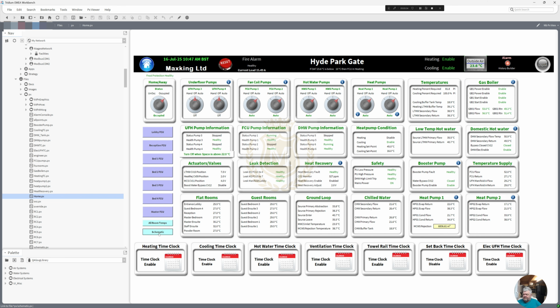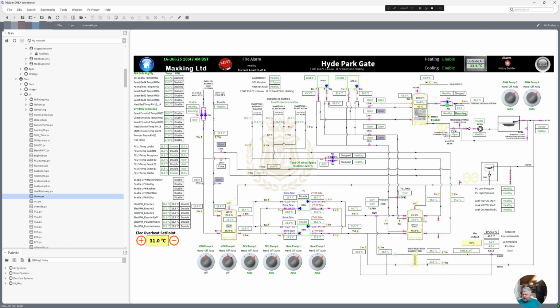And looking at the schematic, we have got two heat pumps here, heat pump 1 and heat pump 2. And as you can see, if heat pump 2 is enabled, we've got the brine of 21.4 coming back from this chilled water tank, and we've got 17.1 going into the chilled water tank. And here we have got fan coils attached to this pipework, so this valve is actually closed, so there's no heating to the fan coils, it's just open on the chilled side.